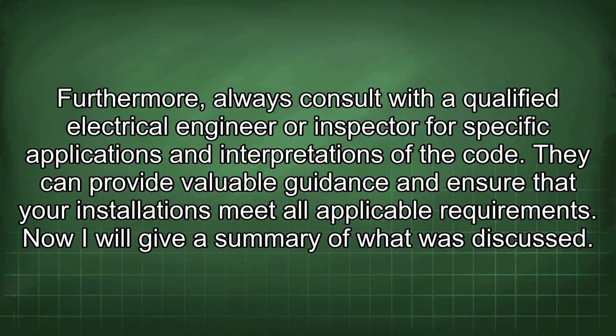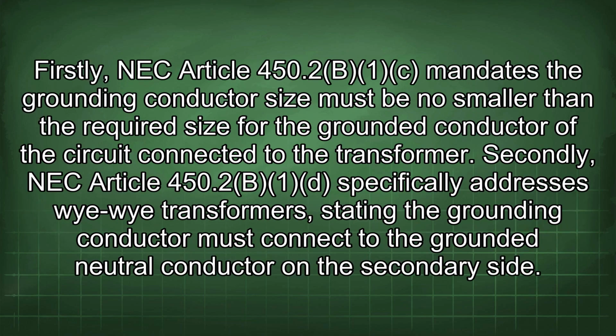Now I will give a summary of what was discussed. Firstly, NEC Article 450.2 mandates the grounding conductor size must be no smaller than the required size for the grounded conductor of the circuit connected to the transformer. Secondly, NEC Article 450.2 specifically addresses Wye-Wye transformers, stating the grounding conductor must connect to the grounded neutral conductor on the secondary side.